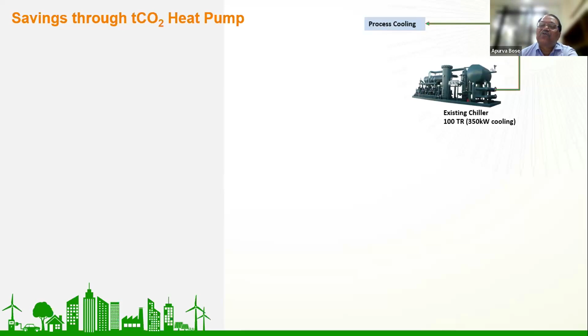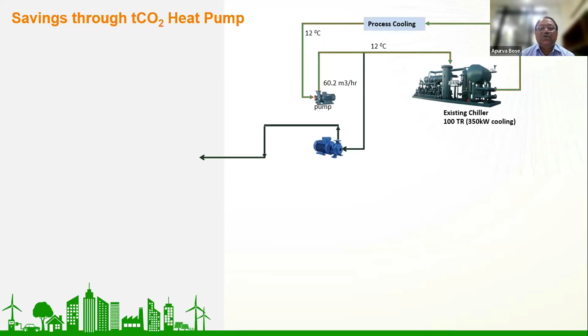What we want to do is decrease the pressure or loading on this particular chiller, so we will take a tapping from this 12 degrees Celsius line and send it to the heat pump. This heat pump, a transcritical CO2 heat pump, will take that at 12 degrees Celsius and can give back at 7 degrees Celsius. In this process, it goes back to the 12 degrees Celsius line, not the 7 degrees Celsius line.